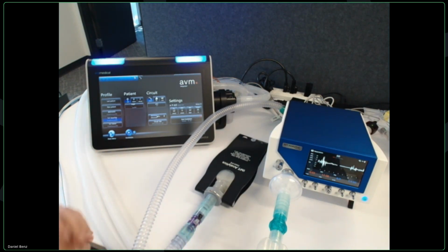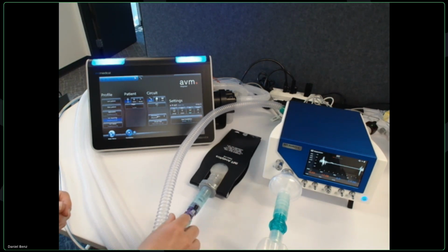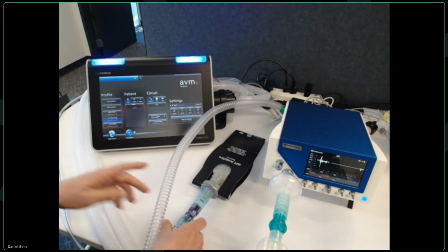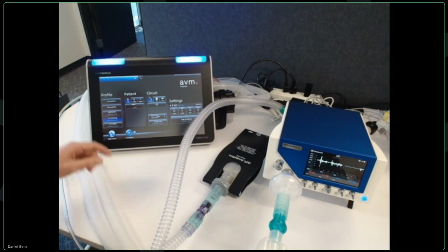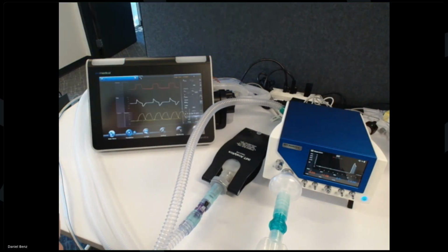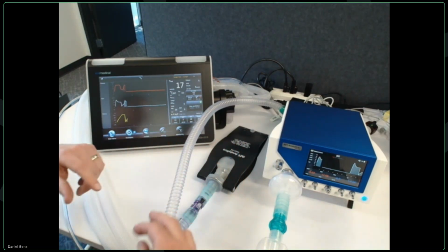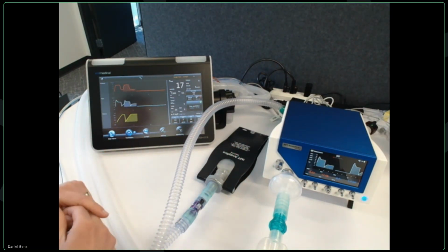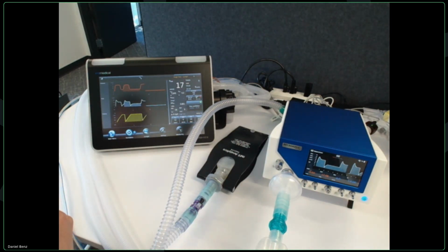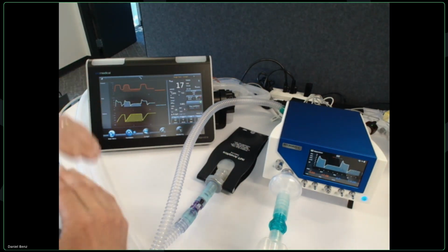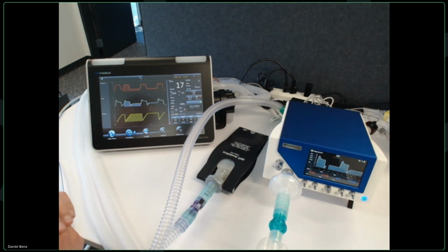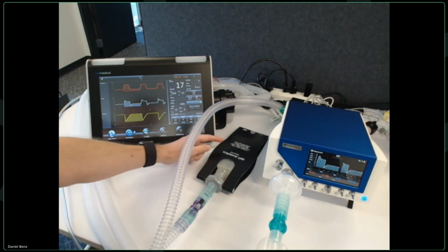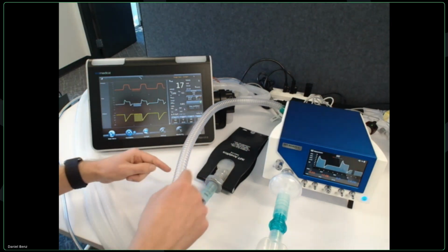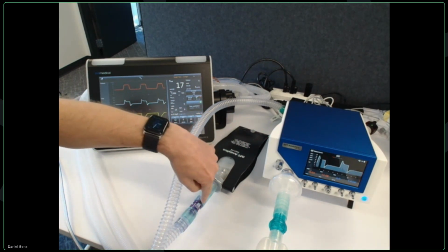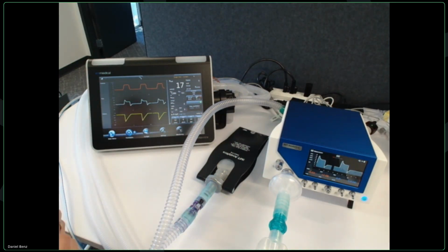So this is very typical with BiPAP ventilators because they don't have an exhalation valve. So in such setups, you might see a defined leakage right in front of the test lung. And when I start the ventilation now, you can probably also hear it. So the BiPAP device applies 2 different pressure levels to the test lung, an upper and a lower pressure level. It's called IPAP and EPAP. And the volume that comes back from the test lung is actually no longer going back to our FlowAnalyser, but leaving here with this defined leakage.